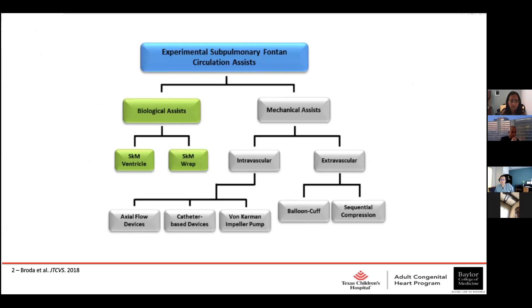There was a report from a UCLA group that used the C-Pulse, which is basically like an intra-aortic balloon pump, but on the outside of the aorta instead of inside the aorta. It was an inflatable balloon placed outside of a valved extracardiac conduit in an in vitro Fontan loop, so not an animal experiment. The report suggested that having the valved conduit and the balloon on the outside of the conduit provided pulsatile flow and increased pulmonary blood flow. In their data, they suggested that the IVC pressure required to do this was on the higher side.